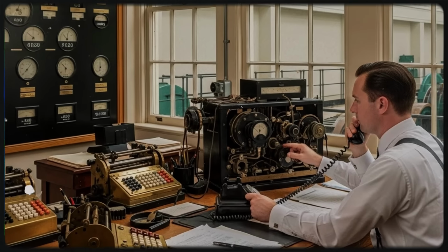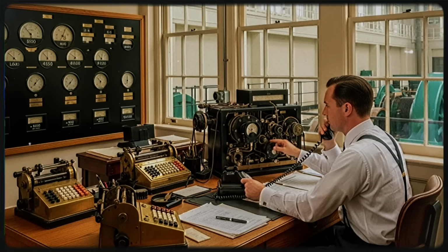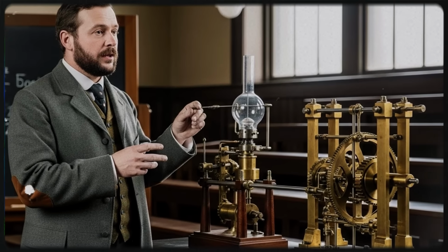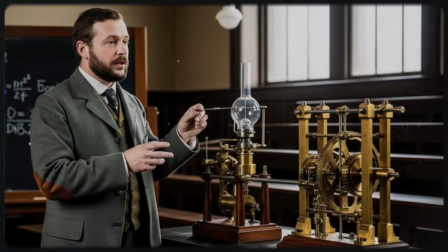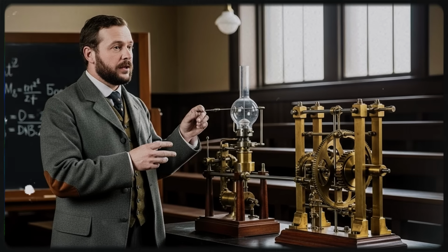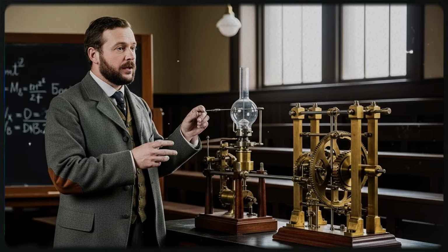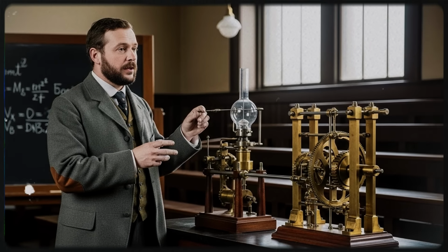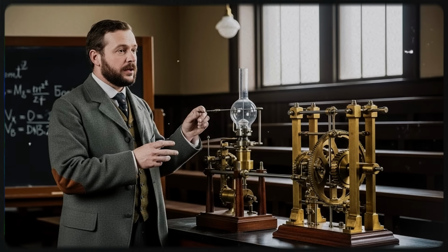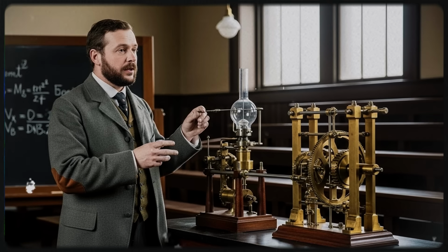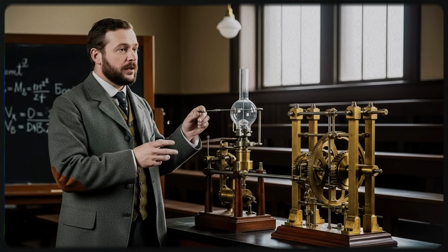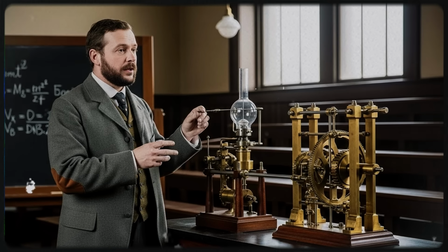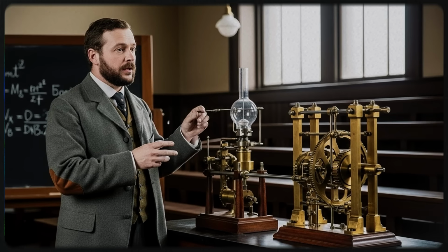Water regulators and turbines adjusted power output in response to load changes. Fourth mechanism, automatic gate regulator in hydraulic turbines. Problem. A hydroelectric turbine connected to an electric generator must maintain a constant speed for a stable electrical frequency, but electrical load varies constantly as users turn equipment on and off. Solution. A regulator that adjusts the flow of water through the turbine in response to changes in speed.